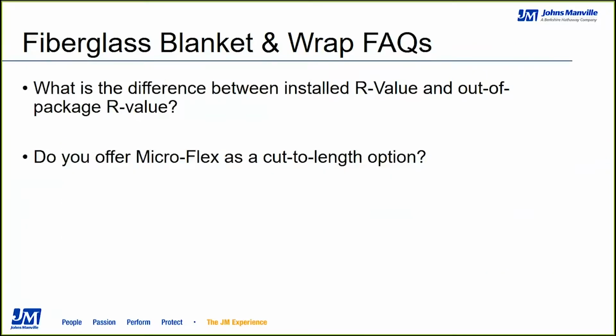Some FAQs. What is the difference between installed R value and out of the package R value? Well, duct wrap is really intended to go on ductwork, typically square or rectangular in shape. And if you think about the 4 corners of a rectangle, that duct wrap is always going to experience compression at those corners in order to get a nice quality installation. Therefore, the installed R value assumes a 25% compression of the product to accommodate for those corners. Therefore, you have a higher R value for out of the package versus that lower 25% reduced R value for installed.